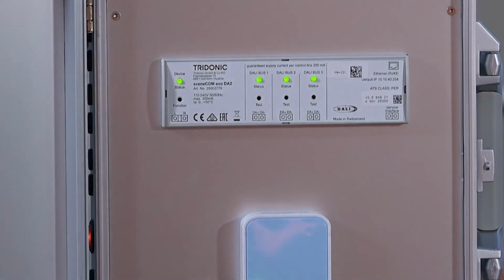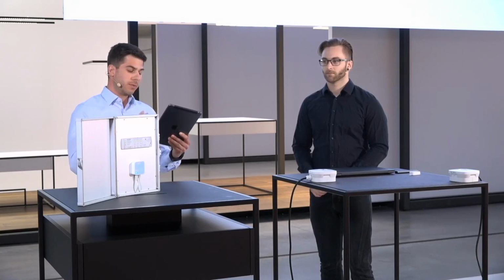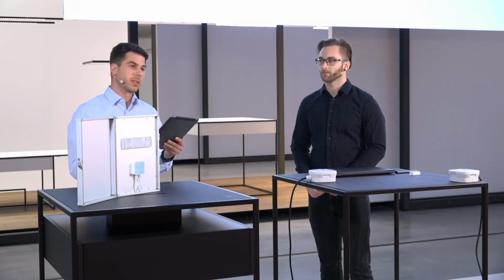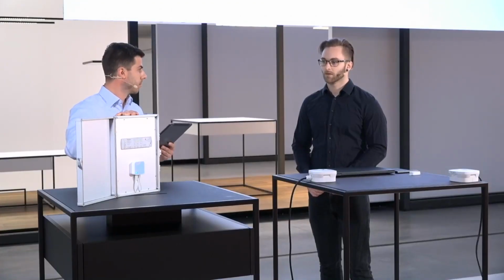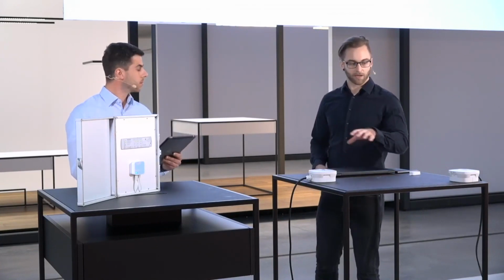But in the case if you also have functional lighting, sensors, and push buttons already in an installed basic DIM wireless network, you probably want to have only the emergency luminaires transferred to the DALI controller. That's why you have here the possibility to choose a control scope, so you can really pick and choose which luminaires you want to control with the DALI controller, the SceneCom controller.